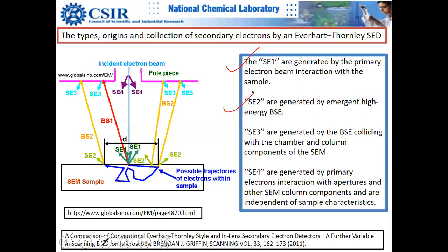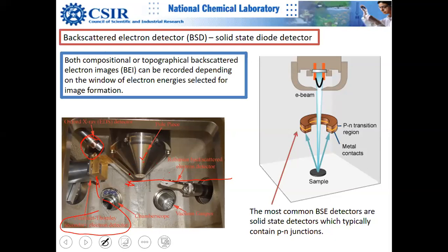SE2 electrons are part of the overall signal, not just SE1. SE2 does not create a serious problem in imaging. The problem is SE3 — generated when backscattered electrons collide with the lens system or chamber walls and cause those materials to emit secondary electrons, which can also be picked up by the detector.